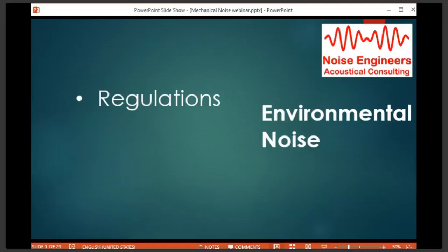Some states don't have a regulation, each city has their own, and some counties do, some don't. Some are very clear about what the regulation is. It could be 50 decibels, 1 hour average LEQ during the night and 55 during the day, or it could be that it just can't be audible inside a home, or can't be a nuisance, or can't be disturbing.